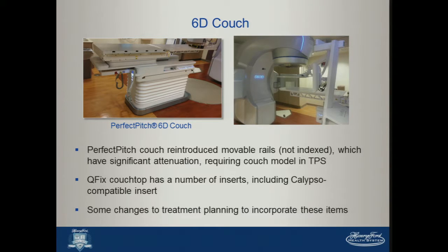And then, of course, you have to pay attention for different treatment techniques. If you're treating spine, for example, previously, before we went to the Edge, we didn't have to worry at all about rail position, just attenuation through a flat couch top. Now we have to take care, and the therapists have to take care, that the rails are moved out of the way of the beam, so none of the beams is entering through the movable rails. So that's one complication with this. QFix has a number of couch inserts with this couch top, including a Calypso compatible insert that reduces the impact on the electromagnetic tracking, but has a slightly higher attenuation. So we had to make a number of changes to our treatment planning approaches to accommodate this, nothing huge.